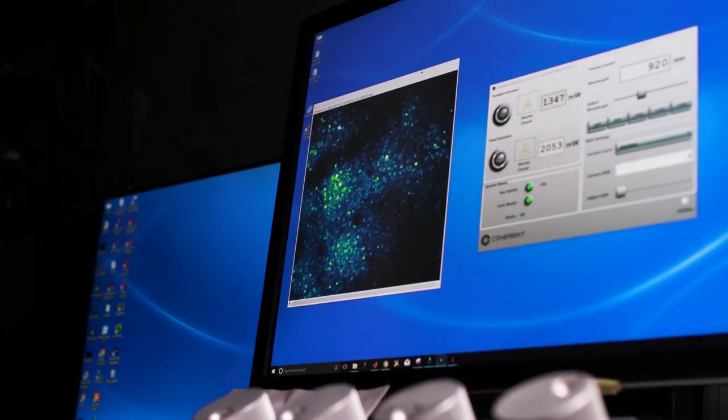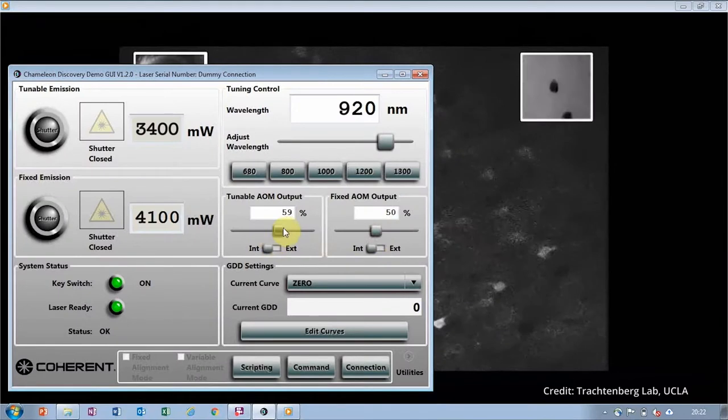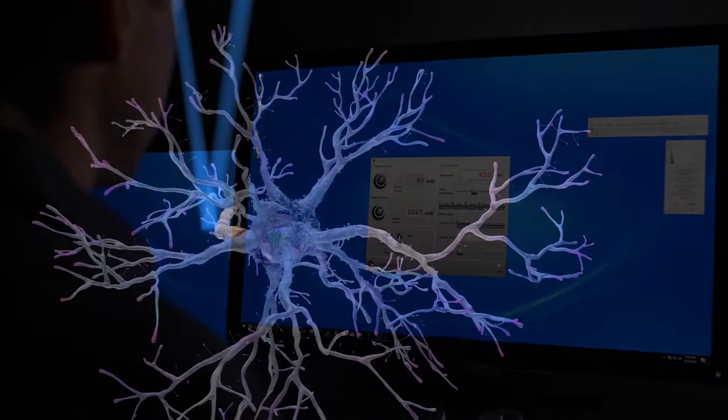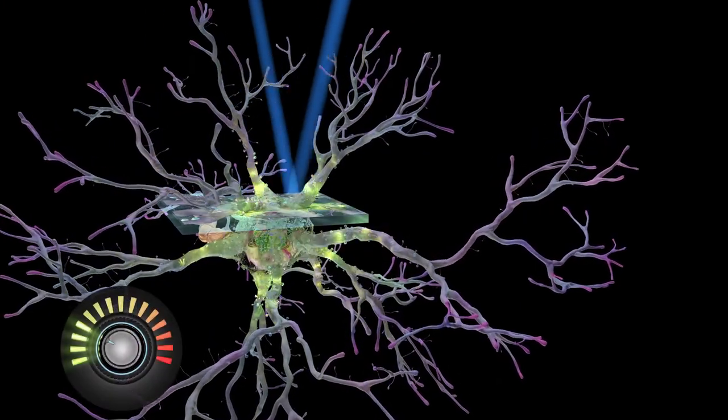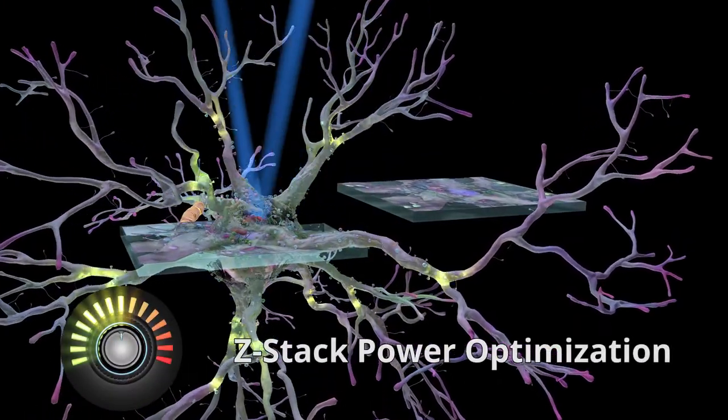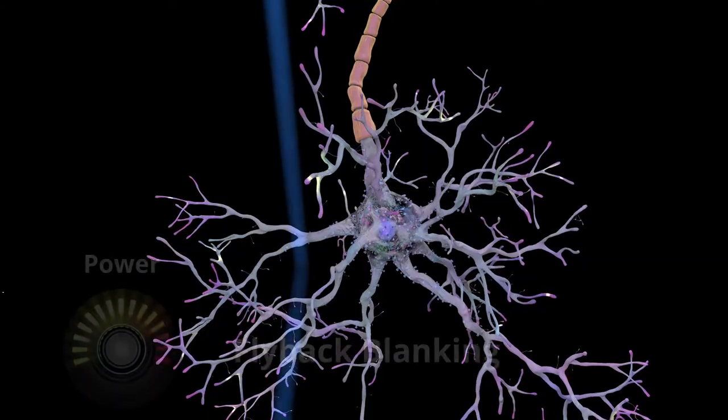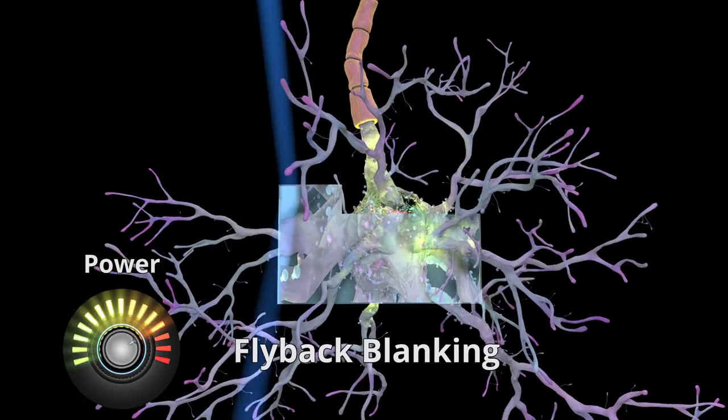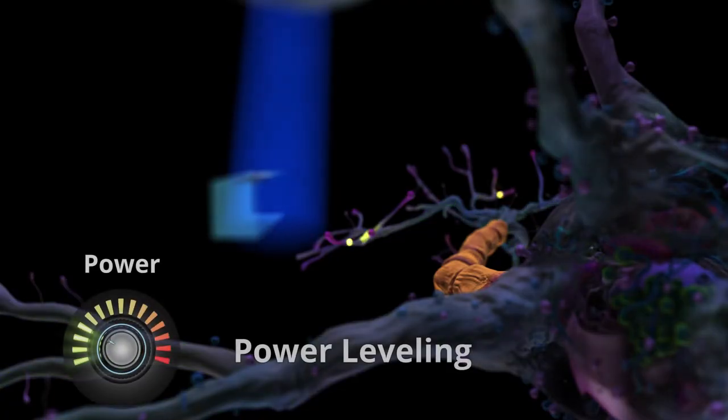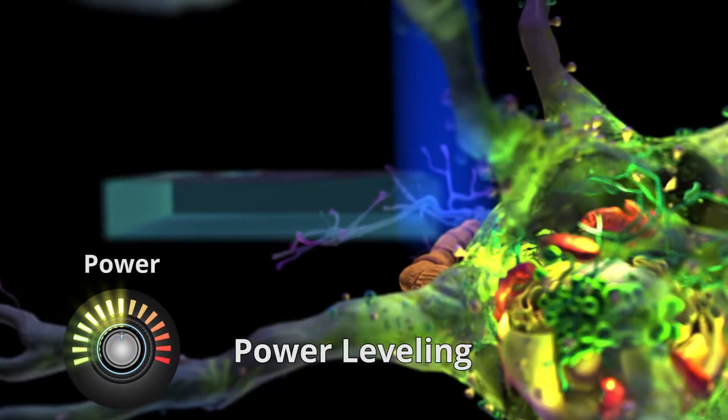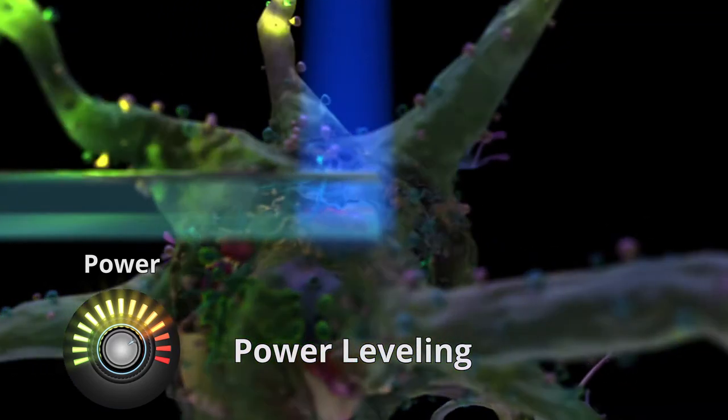Take full control of laser power for safer and faster microscope alignment as well as the full suite of high contrast fast rise time power control methods routinely used for high-speed two-photon imaging such as Z-Stack power optimization, fast raster scan flyback blanking, and power leveling for fast resonant galvo scanning across lines to give uniform noise-free image frames.